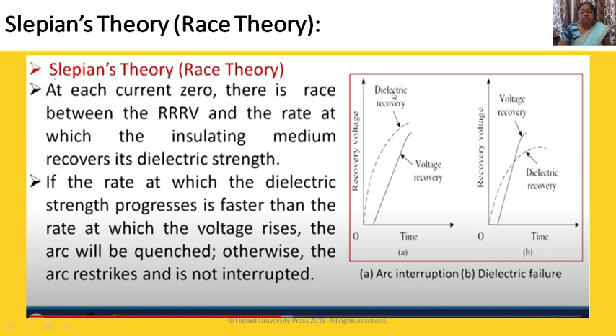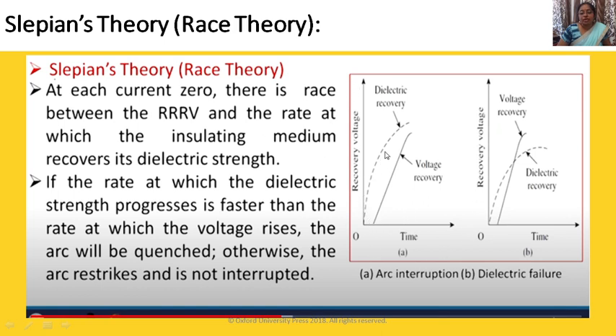By this diagram, you will get a clear idea of dielectric strength and restriking voltage. At each current zero, there is a race between the rate of rise of restriking voltage and the rate at which the insulating medium recovers its dielectric strength. If the rate at which dielectric strength progresses is faster than the rate at which voltage rises, the arc will quench; otherwise the arc restrikes and is not interrupted. In the first graph, you can see the dielectric voltage is on the upper hand over the voltage recovery — meaning dielectric strength is greater than the restriking voltage — and arc interruption occurs.